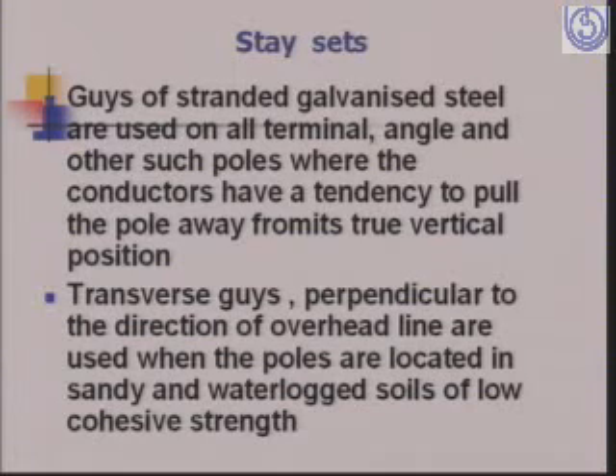We then have the stay sets. Guys of stranded galvanized steel are used on all terminals, angle and other such poles where the conductors have a tendency to pull the pole away from its true vertical position. Generally, we see that the poles tilt away from their normal vertical position. To keep them in place, these stay sets are provided. Transverse guys perpendicular to the direction of overhead lines are used when the poles are located in sandy and waterlogged soils of low cohesive strength.